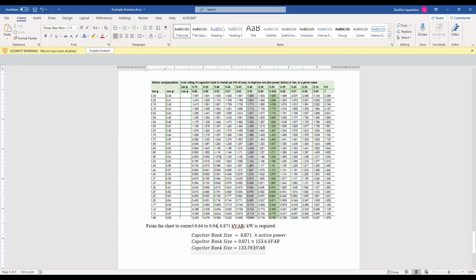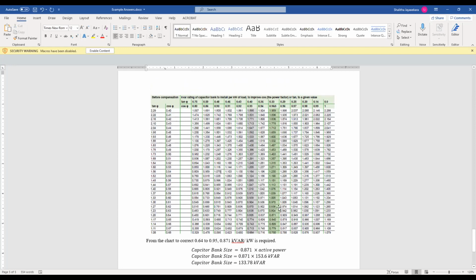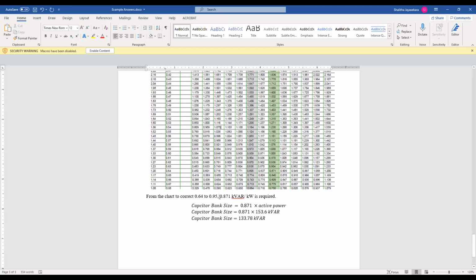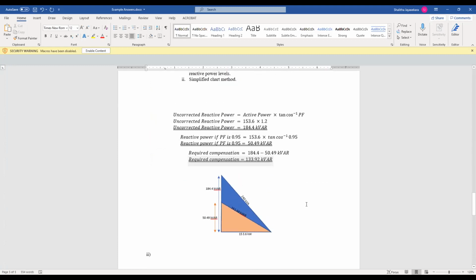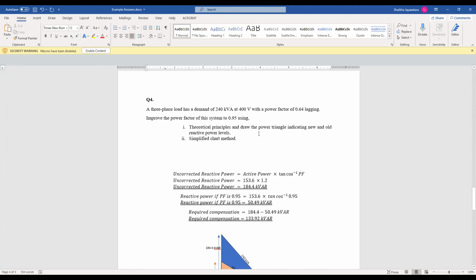See, this should be 0.95. So 0.871 kVAR per kilowatt. In the chart, you are going to find this value. Then you are going to multiply this value by the active power level available in your system. So how are we going to find the active power? We already calculated the active power earlier.